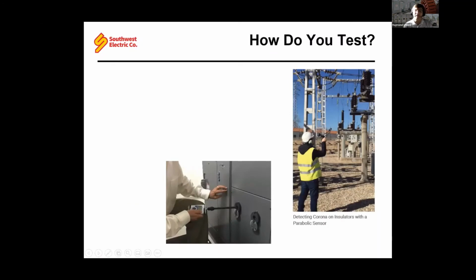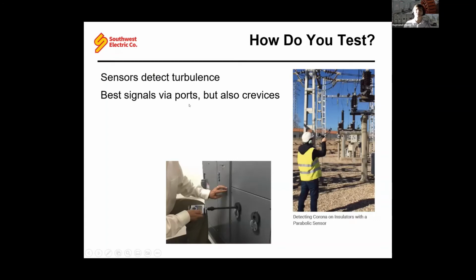So what this looks like is a little device, and you can put it into a port in your enclosure that you can install, or you can do it even through the seams. It's not as good of a signal, but it is still a signal you can act upon. Or when it's high voltage equipment, you can just point it toward the equipment, and it'll detect those vibrations as well. Again, the ports are probably the best signal quality you're going to get.